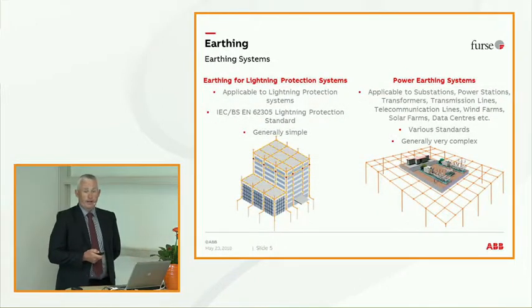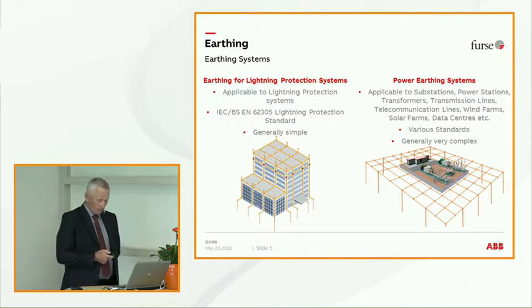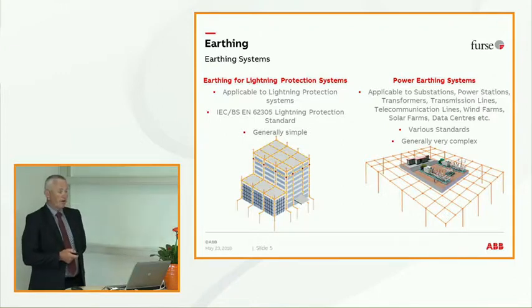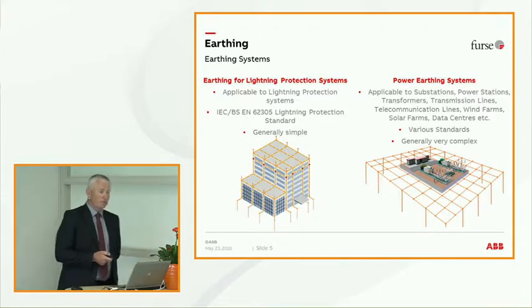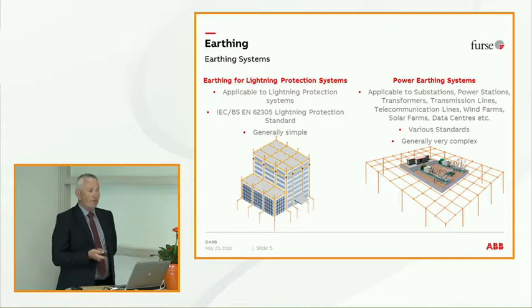My main topic today is general earthing. Earthing is not only for lightning protection, it's also power earthing as well, and there are differences between these. When we're looking at earthing for lightning protection systems, I know there are several lightning protection systems. I'm going to talk generally about the IEC 62305. This is the one that we've adopted in England and is recognised all over the globe.